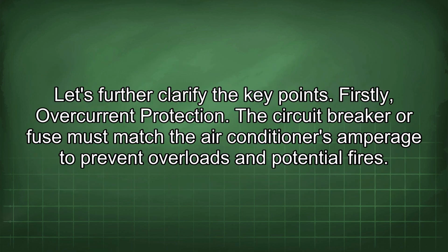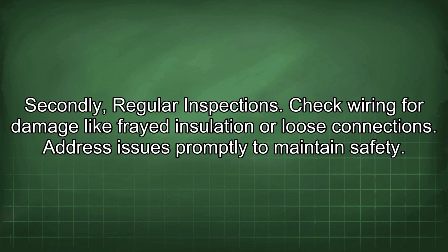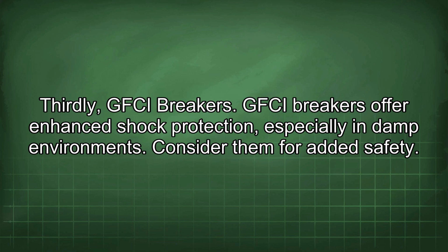Let's further clarify the key points. Firstly, overcurrent protection. The circuit breaker or fuse must match the air conditioner's amperage to prevent overloads and potential fires. Secondly, regular inspections. Check wiring for damage like frayed insulation or loose connections. Address issues promptly to maintain safety. Thirdly, GFCI breakers. GFCI breakers offer enhanced shock protection, especially in damp environments. Consider them for added safety.